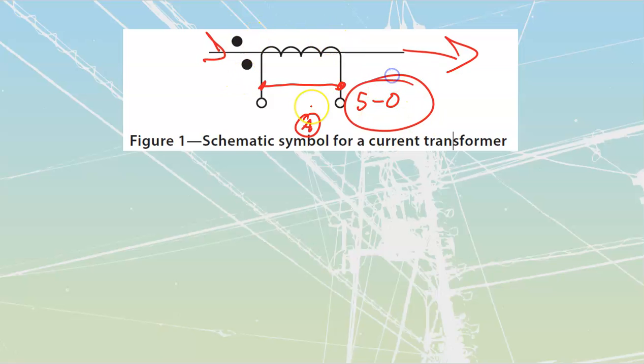What's the maximum amount of current? Five amps, because it's all driven off of what we pull through that main bar. Whatever we're pulling is the main load on the system, and that's driving amps through there. Those amps just see a reflection anywhere between 0 to 5 amps. This whole winding is rated for 0 to 5 amps, so whether I'm passing that 0 to 5 amps through an ammeter, or through a bridge placed across here, it makes no difference — it will not overload it.